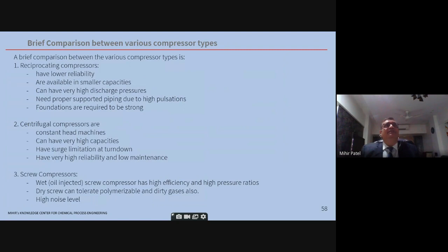Here I have given a brief comparison between various compressor types. Reciprocating compressors, as you can see, have lower reliability, smaller capacities, very high discharge pressures. The piping has to be very well supported for the pulsations. Foundations have to be strong. Centrifugal compressors are constant head machines. They are similar to a centrifugal pump basically. They can have very huge capacities. They are not economical in small capacities. They have a surge limitation at turndown. I have seen a compressor surge when I was in SABIC, Saudi Arabia, and it makes a horrible racket. You cannot stand there. So one has to always operate above the surge limitation. Reliability is very high and they're low maintenance.